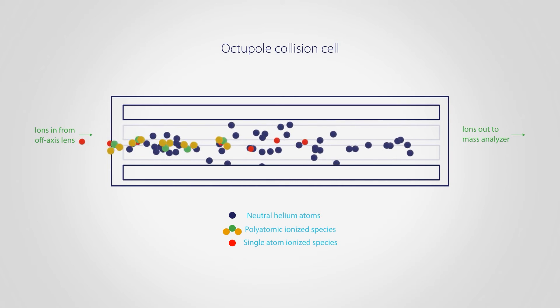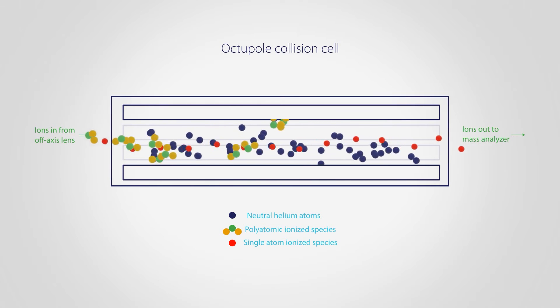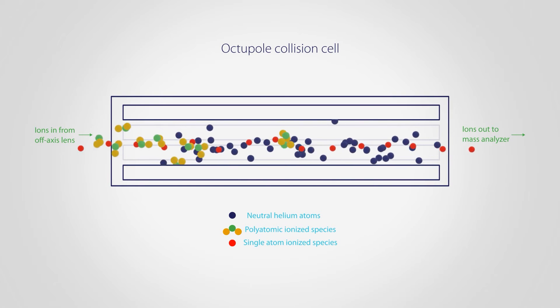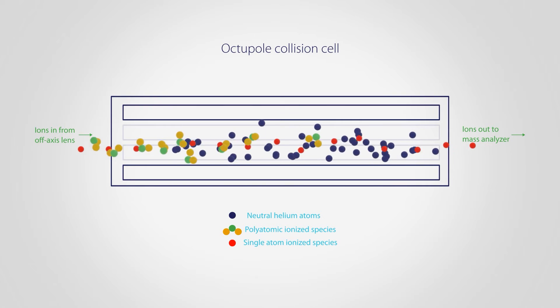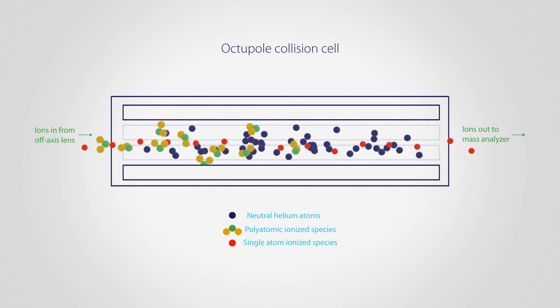The polyatomics thus lose a greater amount of kinetic energy than the monoatomic ions. A small repulsive electric field is applied at the exit of the collision cell as a barrier. Only monoatomic ions have enough kinetic energy to overcome the barrier, while the slow polyatomics are prevented from traveling further.